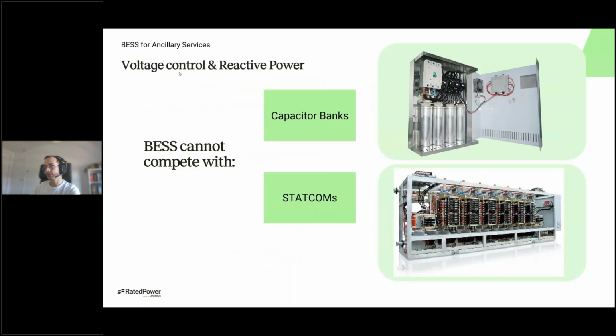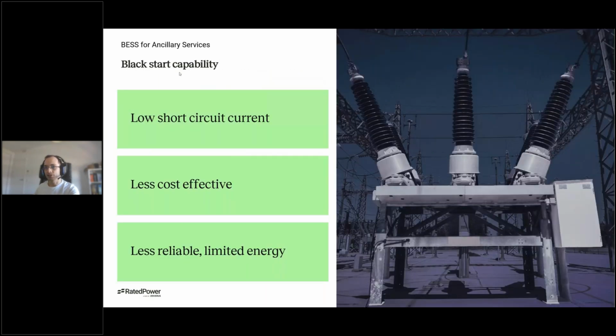So for voltage control and reactive power, long story short, batteries typically cannot compete in terms of price with capacitor banks and statcoms. So there will be virtually no projects where the main objective of a battery system is to have voltage control. Then for black start capability, there are some limitations for batteries. First is that they are not able to provide large short circuit current, so they have low short circuit current. This is interesting because large generators might require a high short circuit current to turn back on. They are also less cost effective than other solutions, and finally they are less reliable and they have limited energy availability. So in periods of crisis, typically pump storage or diesel generators are used.